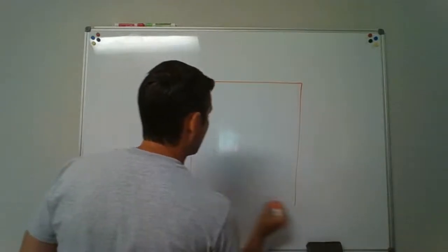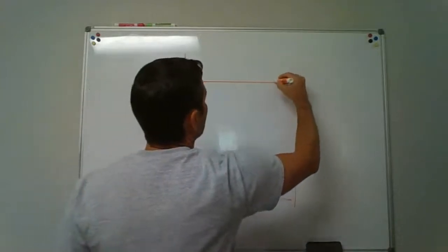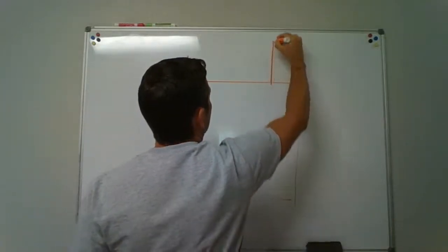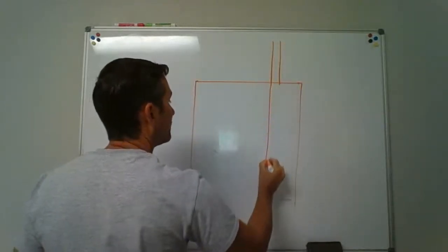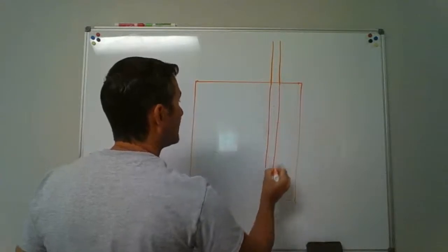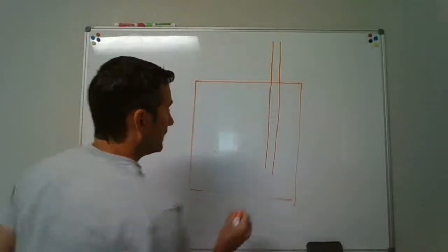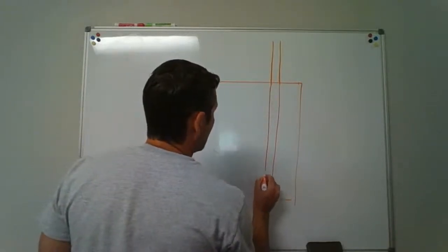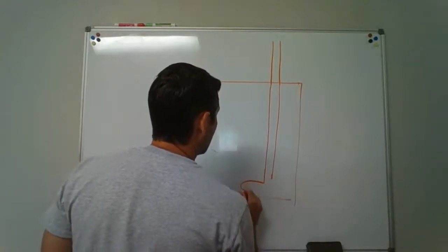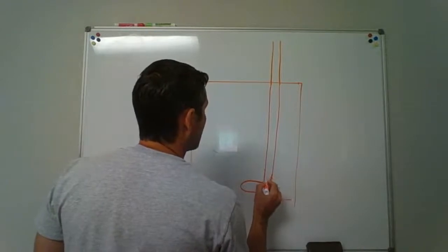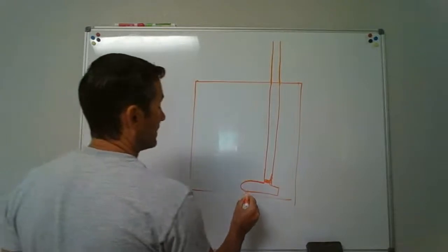There's your tank. Okay, this is a removable lid. It's bolted down. We've got the discharge line coming out. There's the discharge line where you've got your check valve and full open shut-off valve. That comes right down through. There's a gasket that goes around and will seal off around that pipe as it goes through the lid. That's coming down and is going to connect to this pump here. That's typically going to be a female thread. You might thread a male adapter in there and screw it on, so we've got that sitting down here.